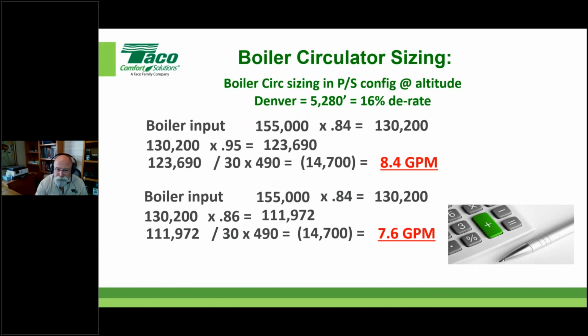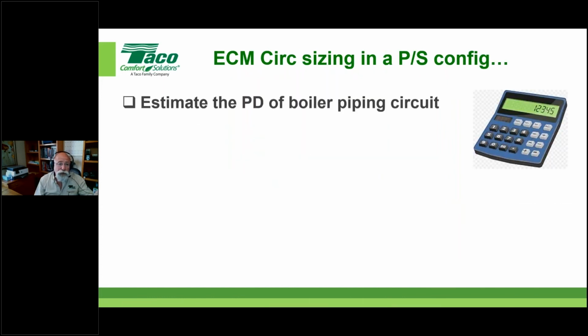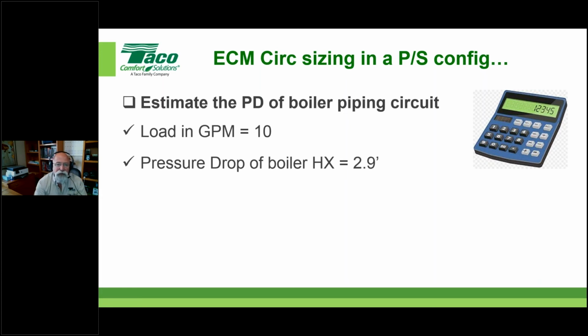Hopefully my point's made. So anyway, in order to do this right, again, these are generalizations, not having the boiler's manual available at midnight, New Year's Eve, etc. We just have to estimate what the pressure drop of the boiler piping circuit is at that given load. I'm showing you the load being 10 gallons a minute, right? Well, the pressure drop of the boiler heat exchanger, if it's a water tube style heat exchanger, might be 3 or 4 times this number. Okay, always try to look it up if you can get somewhere online. Try to figure out what it is. But these very popular fire tube designs are much lower pressure drop. They're just buckets of water that we're pumping water through. There's not a lot of resistance.